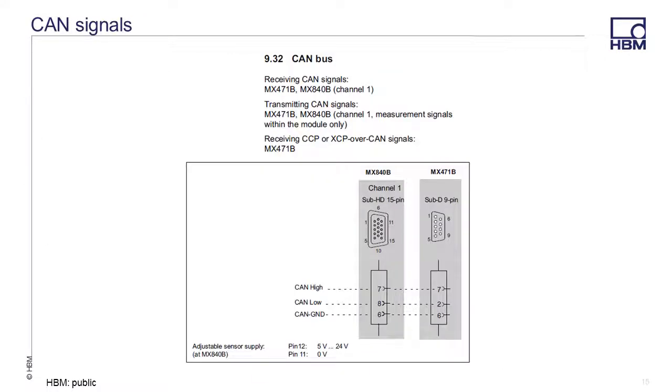There are two QuantumX modules that support CAN signals, the MX840B and the MX471B. The MX840B supports CAN signals only on channel 1 and can provide sensor supply. The MX471B does not provide sensor supply.